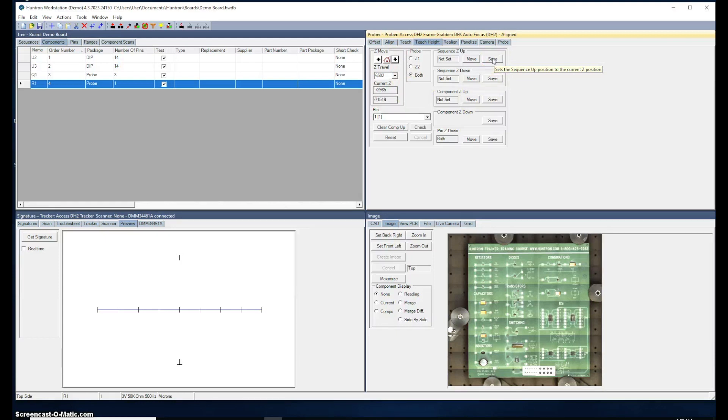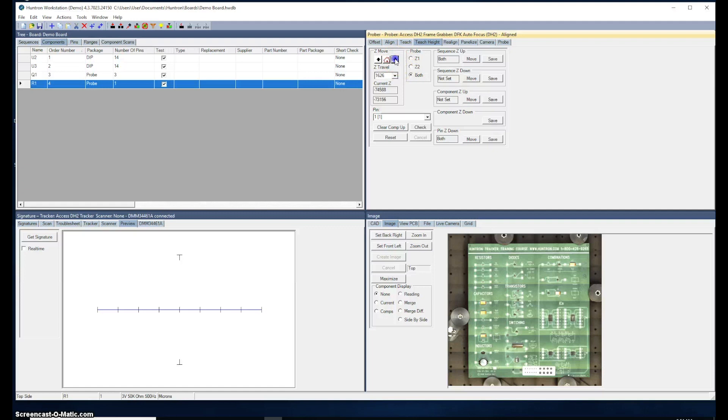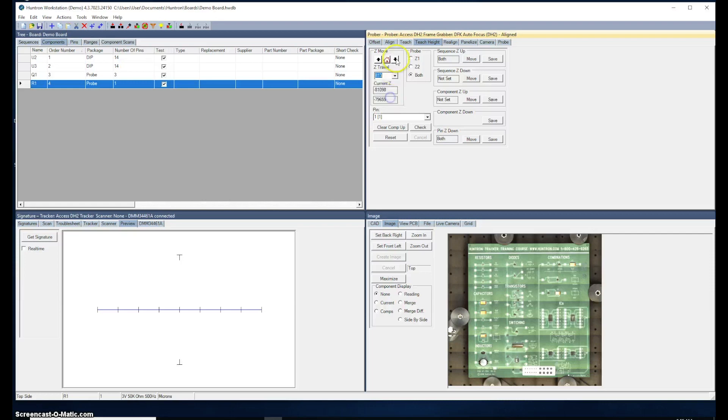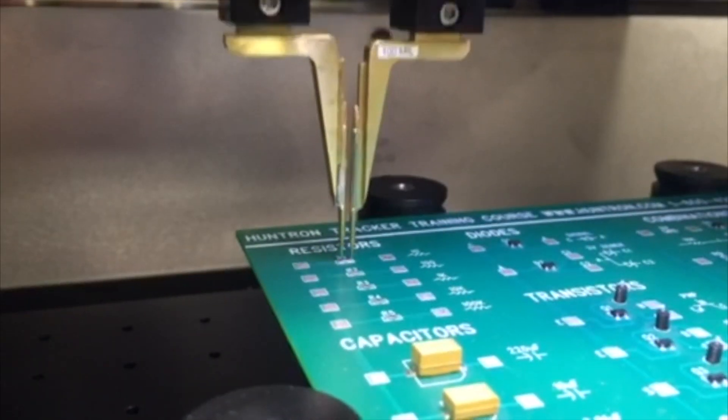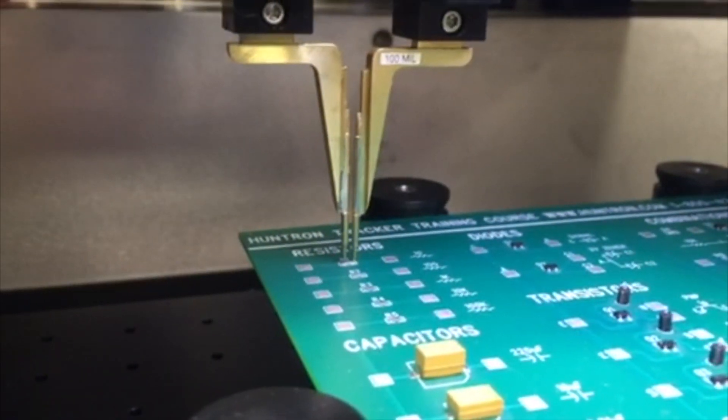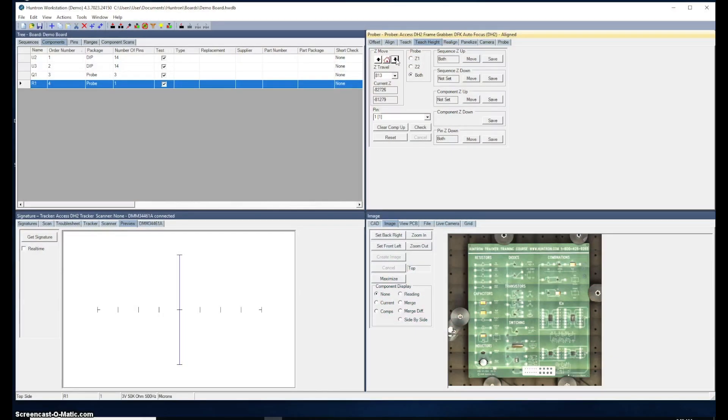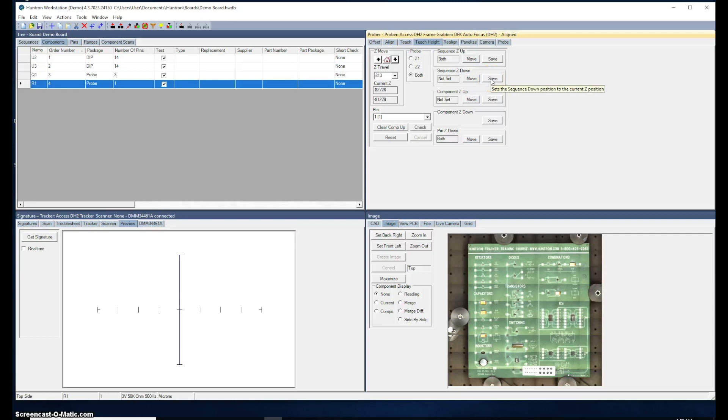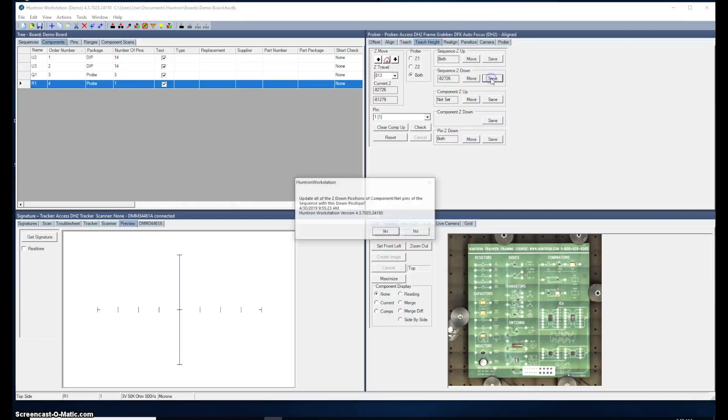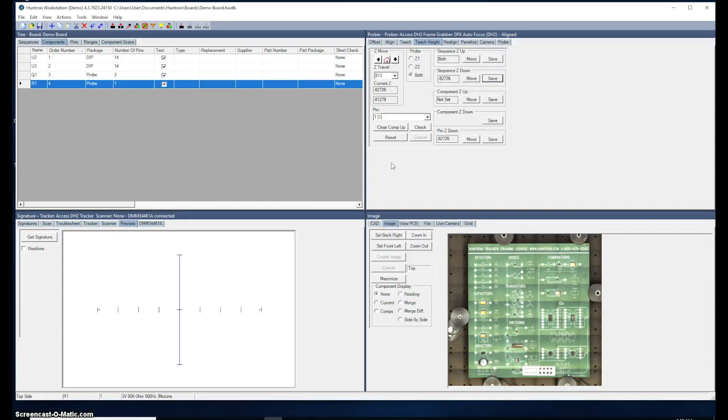The next thing to do is to lower the probe down until it makes contact. You should see a signature down the bottom left in the signature pane when we make contact. I'm getting close. I'm going to change my distance a little bit shorter distance now. Okay, so we have contact. And we'll generally push the probes down a little bit farther past contact to make sure we get good contact. These are spring probes that we're using in the probe tips. So we'll save that as the sequence Z down. That means this will be the down position as it's probing for all of the components in the sequence.